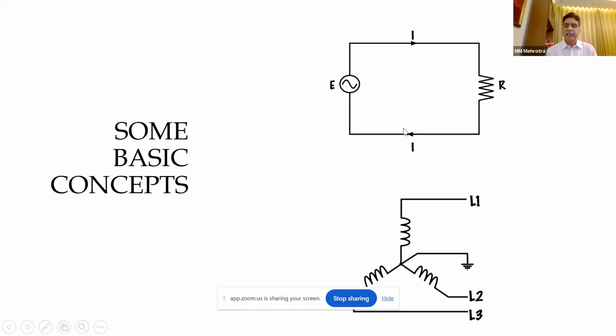Now coming to our next figure, the phase conductor and neutral conductor carry the same current I. In case of three phase, each phase conductor carries some current, and the neutral conductor carries the vector sum of these three currents. If these three phase currents are the same, the neutral current will be zero. So ideally, the neutral conductor in a three-phase system is not required to carry any current. If there is unbalance, some current will definitely flow, generally in the range of 20 to 30% of the full load current. That means the neutral of a single phase conductor will be of the same size as the phase conductor, and the neutral of a three phase system will be half the size of the main conductor.